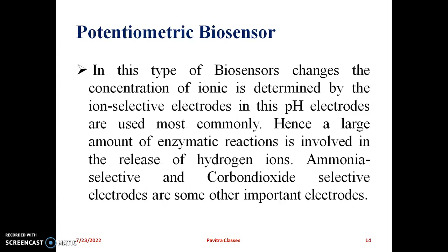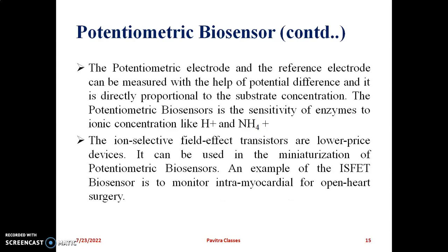Next is the potentiometric biosensor. In this type, the change in concentration, usually ion concentration, is measured. Ion-selective electrodes are used for ionic determination. In this, pH electrodes are also used, since a large number of enzymatic reactions involve the release of hydrogen ions. As it is ion selective, the hydrogen ions will be released. Ammonia-selective and carbon dioxide-selective electrodes are some other important electrodes used in potentiometric biosensors. The released ions will pass the current and the measurement of the data will take place in the signal recorder. The potentiometric electrode and the reference electrode are measured with the help of the potential difference. It is directly proportional to the substrate concentration. So as the biological material increases, the potential difference also increases.